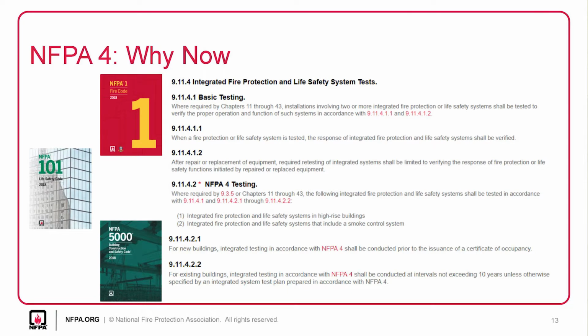That was put into the fire code. The fire code is applicable to existing buildings. So I'm assuming they're amending the fire code to say reference NFPA 4 for testing? Well, this is in the fire code. Because in 909, you need to test with an approved agency. That's for smoke control and stuff though. Correct, this is any integrated system. Yeah, so I don't actually know how they tied those within the fire code, but I would say yes, they're going to tie to each other, where it's going to tell you that you need to follow 4 for any of your smoke control tests.